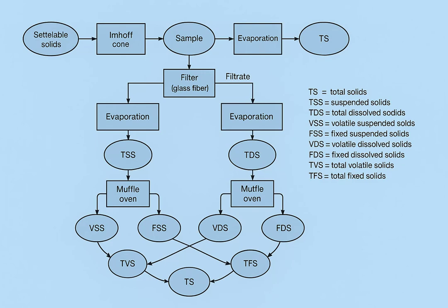Okay, one more. Settleable solids. Sounds self-explanatory. It pretty much is. It's the volume of suspended solids that will settle out of the water by gravity within a set time, typically 1 hour. How do you measure that? Just let it sit? Basically, yeah, but in a standardized way. You use a special graduated cone-shaped container called an Imhoff cone, fill it with a liter of sample, wait an hour, and read the volume of sludge settled at the bottom in milliliters per liter. Very practical. Yeah. Tells you what you can get out easily in, say, a sedimentation tank. Precisely. Key for primary treatment design and operation.